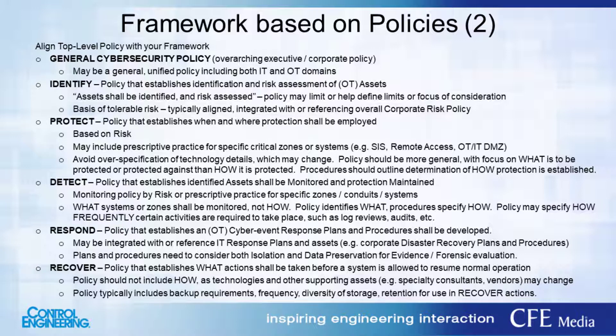I see this policies pyramid as upside down because policy is the top level — a great place to start, answering the why and what, but not necessarily the how. Most companies already have an IT security or cybersecurity policy they can extend to their operational technology and physical plant systems. You need to engage your IT counterparts, find out what existing policies state, and assess whether a separate policy is needed or if you can expand the umbrella policy. Then map back to the elements within the NIST framework domains of identify, protect, detect, respond, and recover.